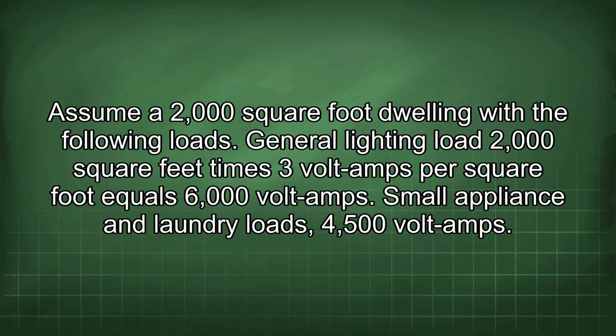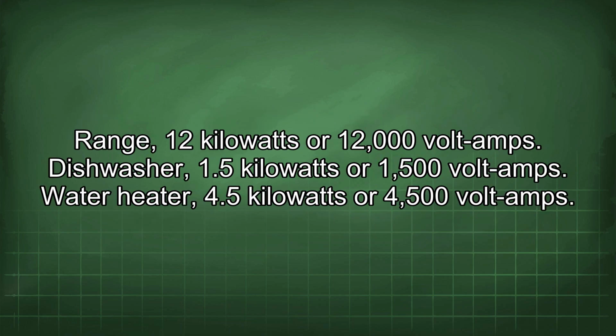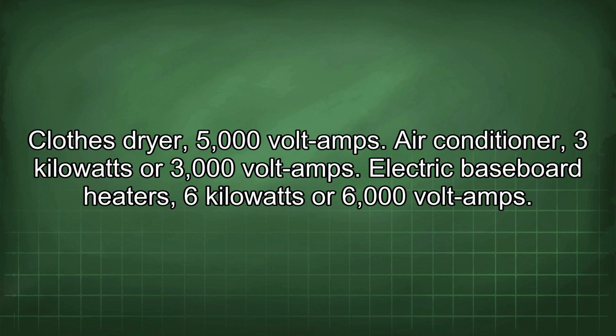Small appliance and laundry loads: 4500 volt amps. Range: 12 kilowatts or 12,000 volt amps. Dishwasher: 1.5 kilowatts or 1500 volt amps. Water heater: 4.5 kilowatts or 4500 volt amps. Clothes dryer: 5000 volt amps. Air conditioner: 3 kilowatts or 3000 volt amps. Electric baseboard heaters: 6 kilowatts or 6000 volt amps.